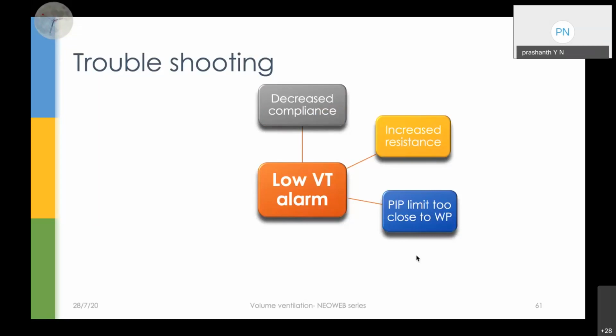So if you have curtailed that, it will alarm. And regarding your PIP limit, we said we need to keep it at least 3 to 5 centimeters of water above the working pressure, or 25 to 30% above it. Suppose the baby is requiring around 18 pressure to deliver a set volume and you have kept your maximum at 18 or 19, let's say. I know that most of the breaths will probably touch 19, some of the breaths go to 20, some of the breaths go to 16. So when it goes above 18 or 19, it will definitely beep. So we need to give that breathing room for the ventilator.